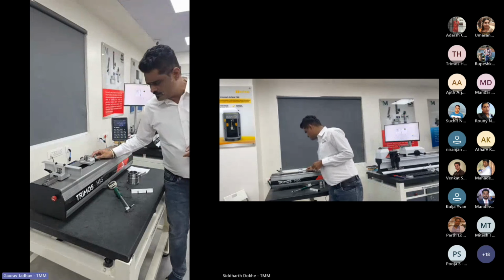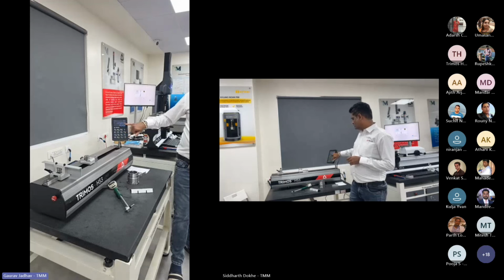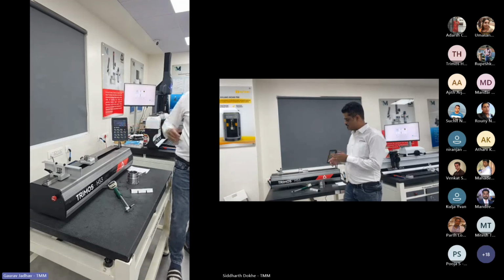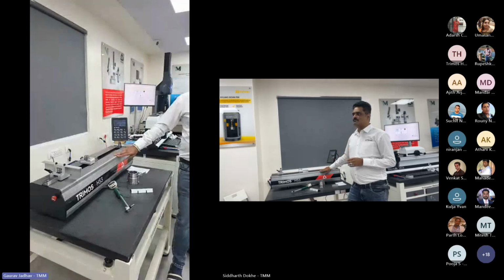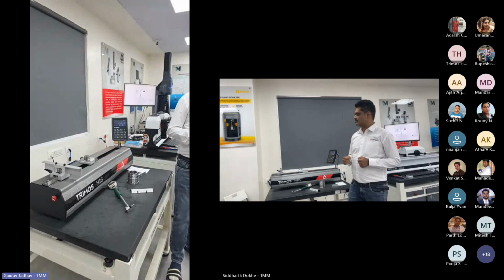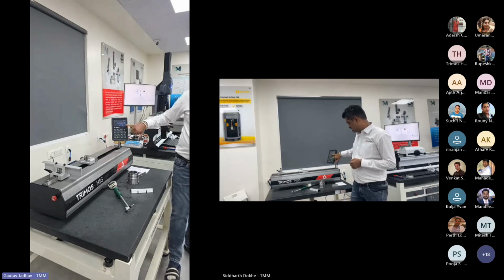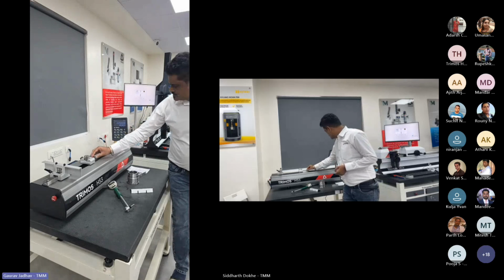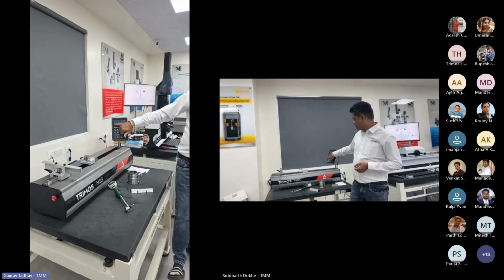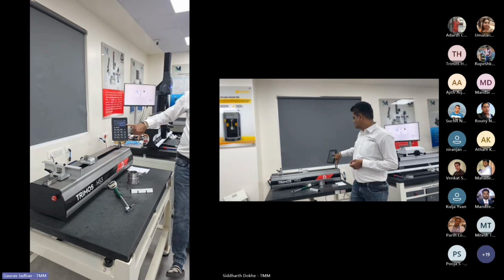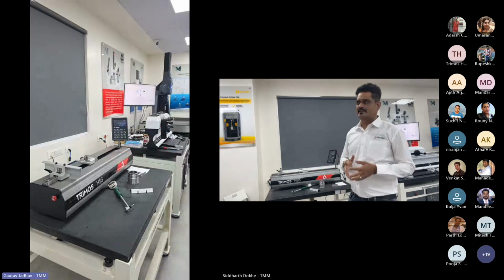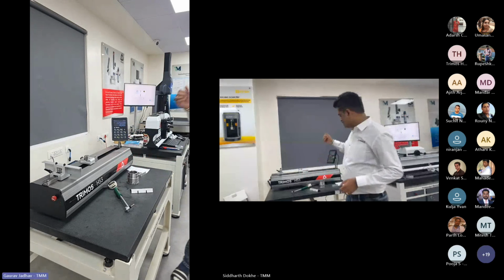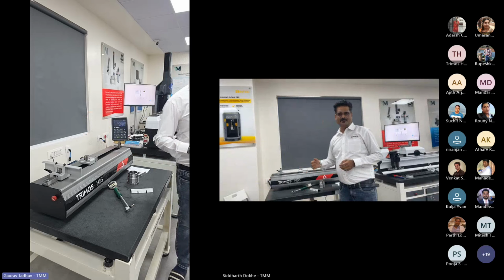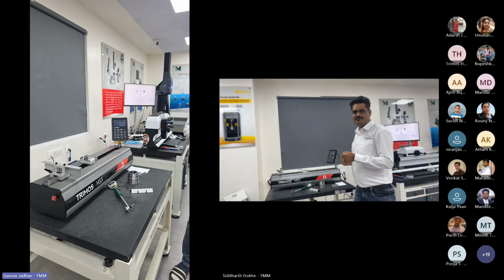Next, the position: what the machine is now, 225.00. The Trimos has used a very powerful motor in this machine, so this position will be fixed after it reaches the actual value. If you see here, if I push this or pull this, the reading will not move. This is because of the very powerful motor used in this machine.